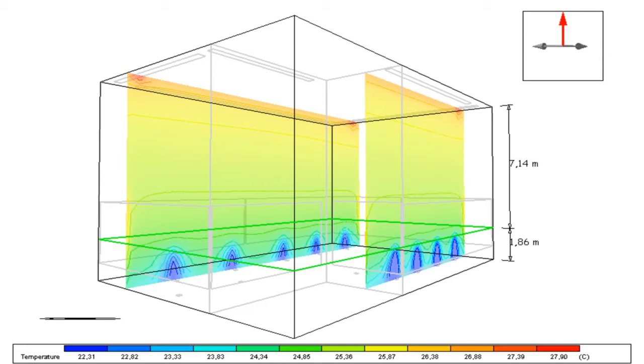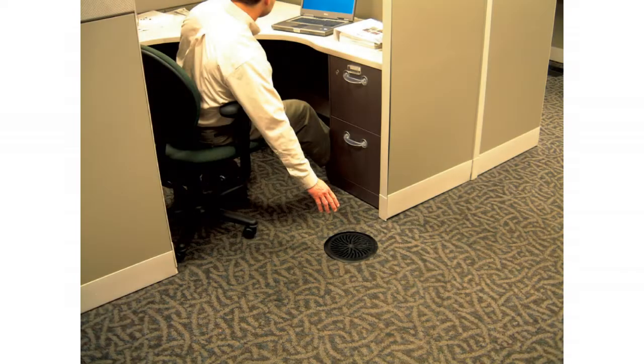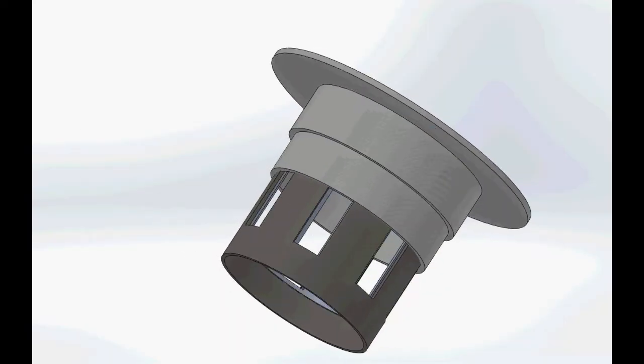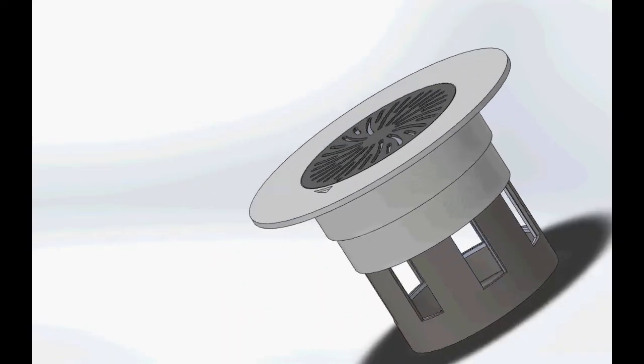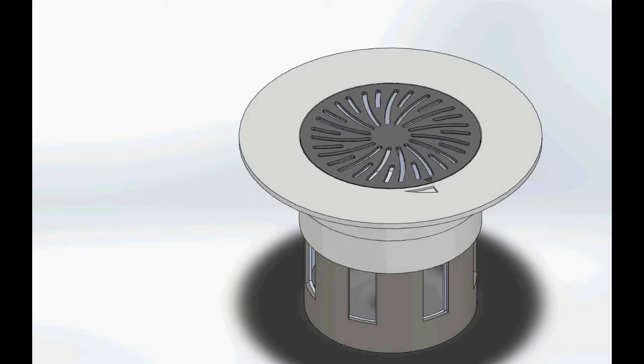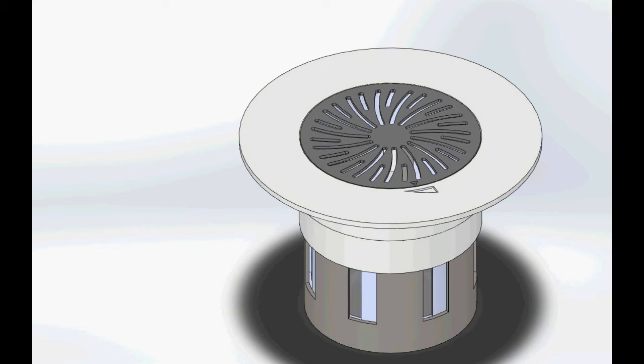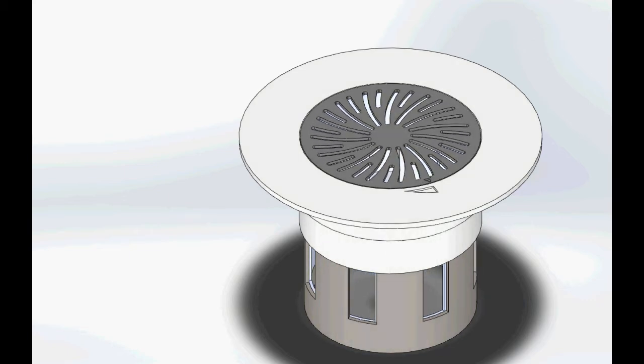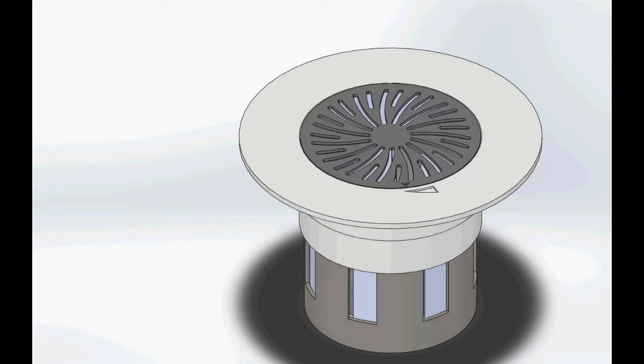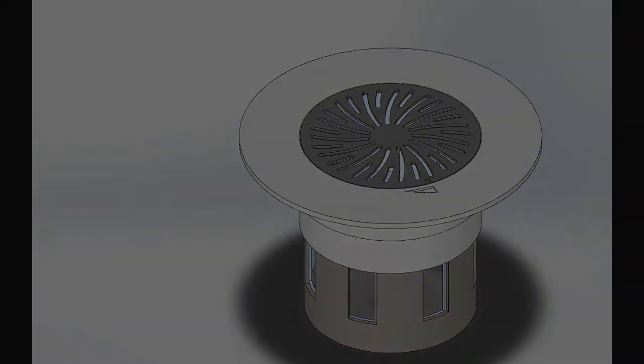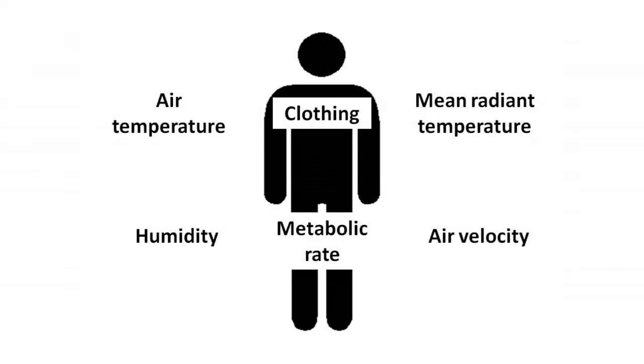This process, known as stratification, has beneficial effects on thermal comfort of the occupants. Furthermore, because of the diffuser layout and density, there is no need for high air inlet speeds and very low inlet temperatures. The occupants could adjust the airflow to suit their individual needs by turning the bars around in the sockets, thus directing the airflow. Recent field research, ASHRAE sponsored research project 1161RP, has found that building occupants who have no individual control capabilities are twice as sensitive to change in temperature compared to occupants who do have individual thermal control. What this indicates is that people who know they have control are more tolerant of temperature variations, making it easier to satisfy their comfort preferences.